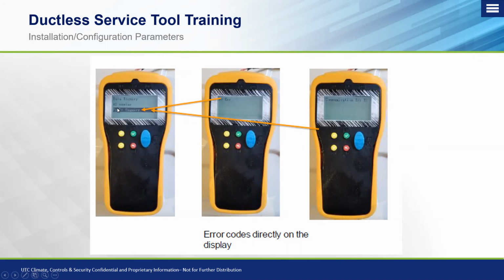So you can see on here, you can have a fault inquiry. And again, unfortunately, this is not a history of error codes. It only displays active error codes. And that is a common request and something that guys wish that we had, a history of error codes, but it only displays active error codes in the system.